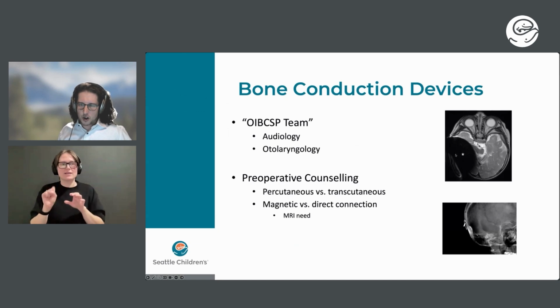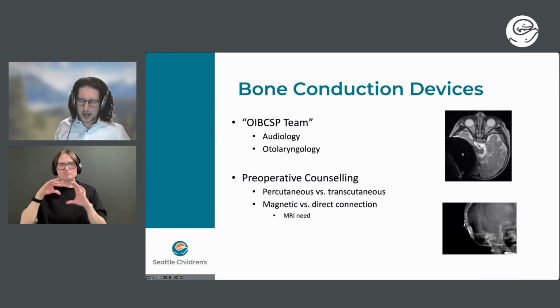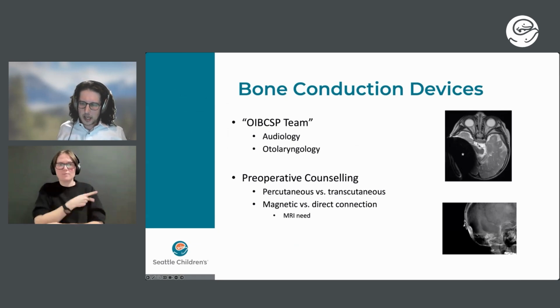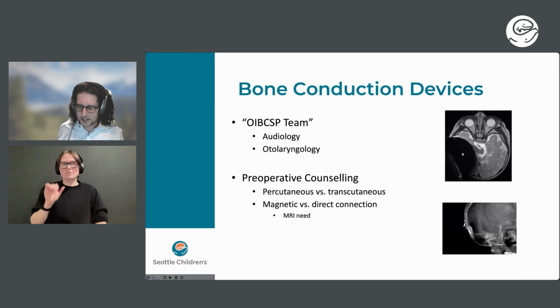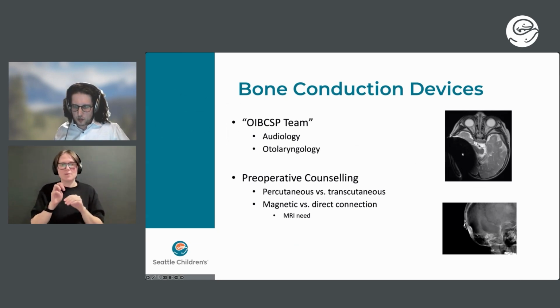So the active devices all contain an implanted magnet, and this magnet will cause some signal artifact under MRI that can make it hard to image that part of the brain. So that can be an issue in patients who need serial MRIs. In the older active devices, just like the older cochlear implants, the magnet was not MRI safe. Here's an example of a magnet moved in the MRI field. But in the more current devices, they do have a magnet that is MRI safe.